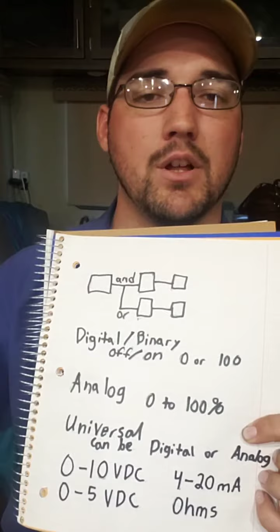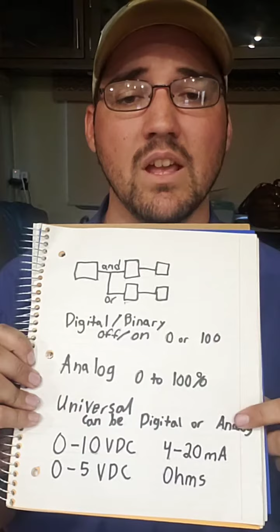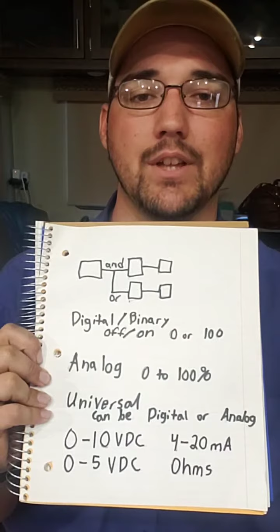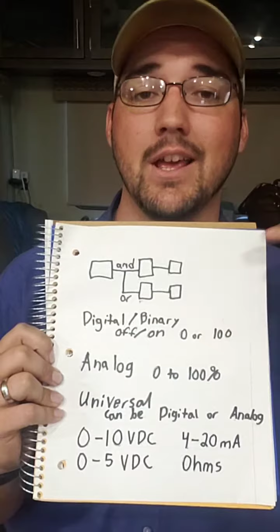So we talked about binary and digital. Those are off and on. We talked about analog, that's 0 to 100%, whether it be input or output. Let's talk about universal. Universal is kind of what it sounds like. It'll have a U instead of an A or a D on that terminal point. If it's a universal point, that means that controller could be programmed, depending on how the logic is written, to do an analog signal or a digital signal. It could be either or, and that depends on what they tell that particular point to do.